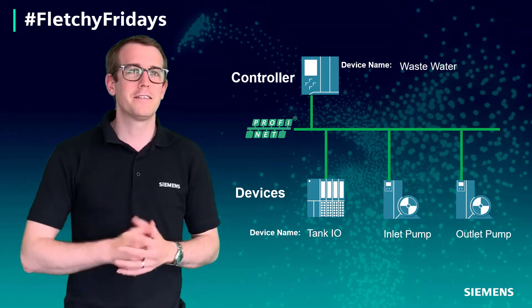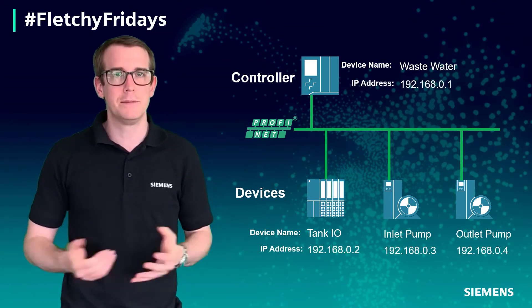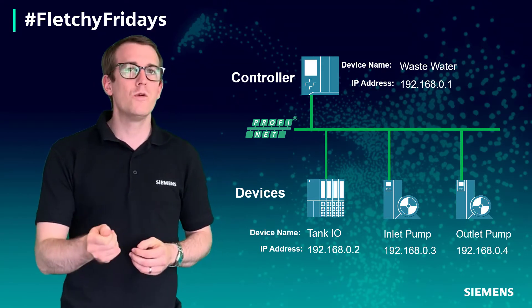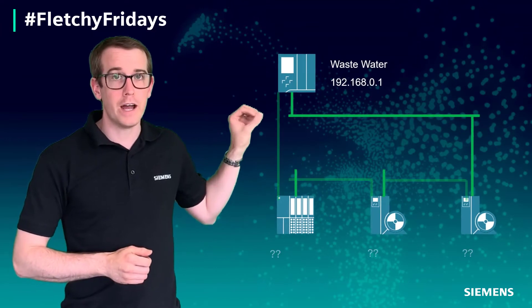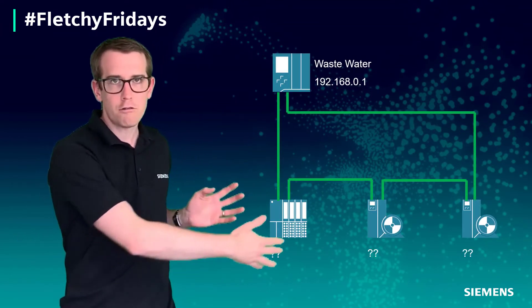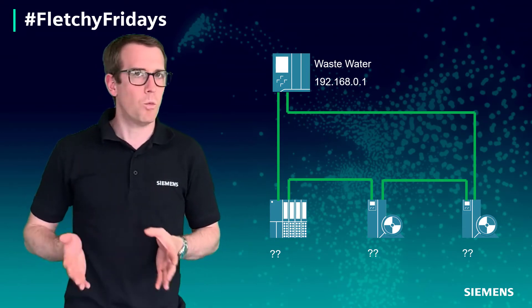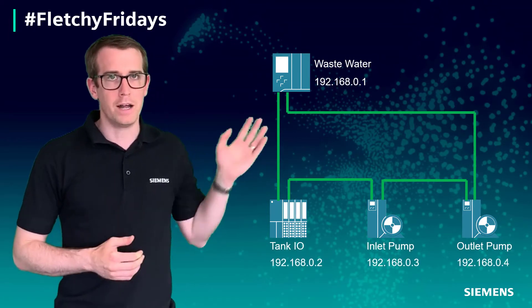On top of this, we do have IP addresses assigned to these devices because it is a TCP based system. What's really cool with ProfiNet though, is if in the controller you define your topology for the entire network, then you don't need to go around all these devices manually telling them what their name is and what their IP address is. It'll get automatically assigned at power up by the controller.